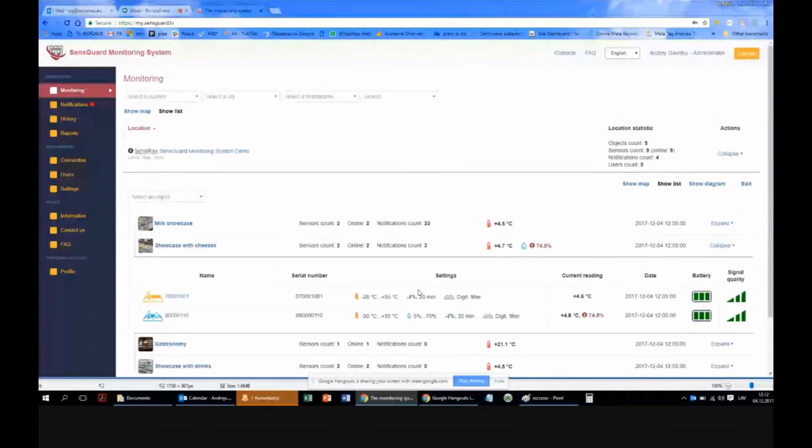We also see the period of time that the sensor is allowed to be outside these min and max temperatures. It means that if the temperature is above 36 degrees for 20 minutes, then I get a notification. If it is only 18 minutes, then not.